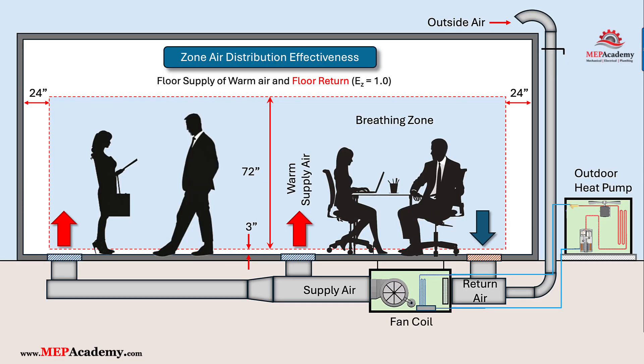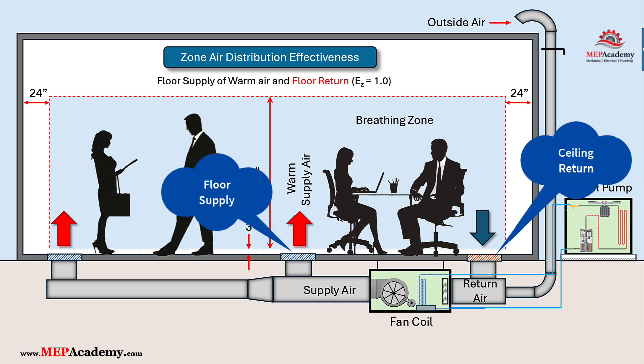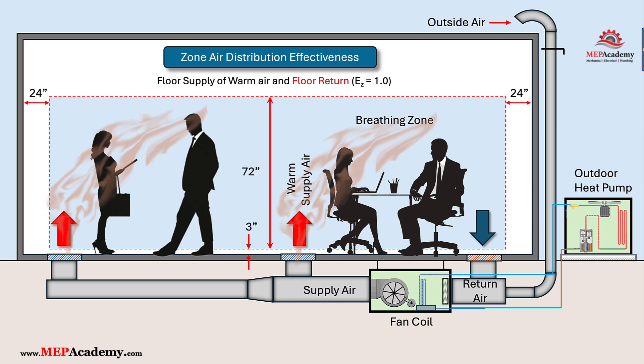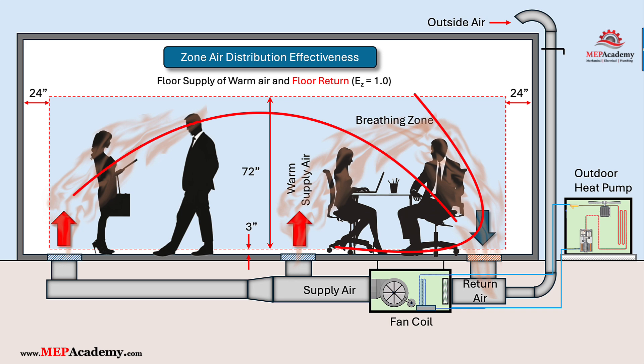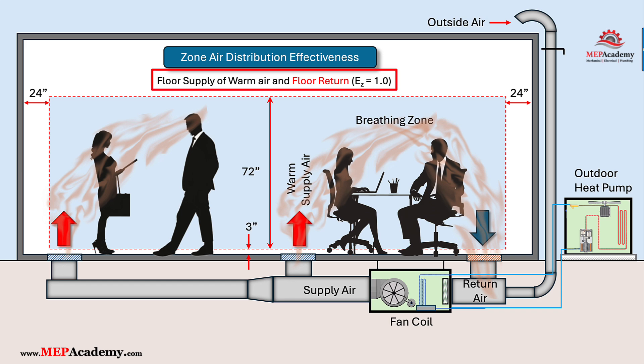The Zone Air Distribution Effectiveness (EZ) is a factor used in ASHRAE 62.1 to account for how efficiently an HVAC system delivers and mixes outdoor air within a given space or zone. It reflects how well the ventilation air is distributed to the occupants' breathing zone, impacting the amount of fresh air needed for adequate ventilation. The effectiveness varies based on how air is supplied and returned, considering factors like supply air temperature and system design. For floor supply with floor return in heating mode, ASHRAE indicates an EZ of 1.0, meaning the value does not add or subtract CFM from the previous calculations.